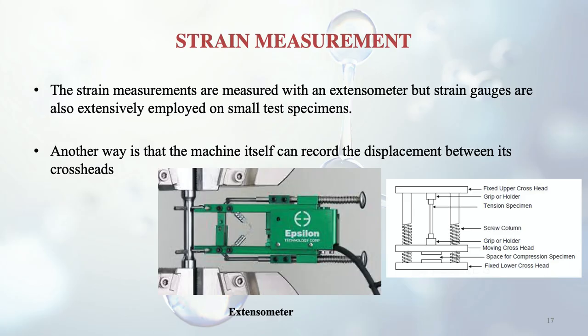Regarding stress and strain: stress is the resistance of a body when a force is applied to it. Strain is the elongation that results. Strain measurements are done with an extensometer, though strain gauges are also extensively employed for small test specimens. Another approach is that the machine itself can record the displacement between its cross heads.